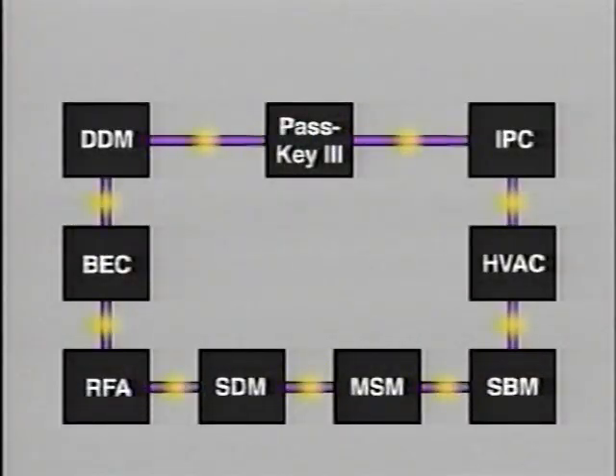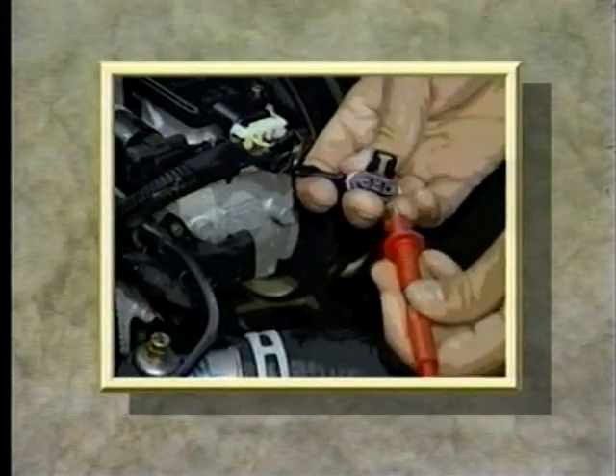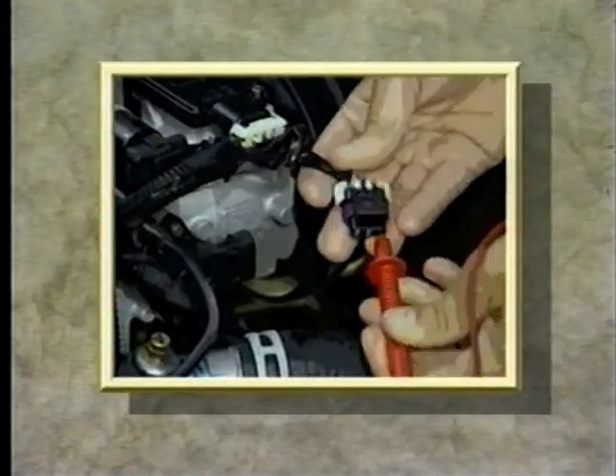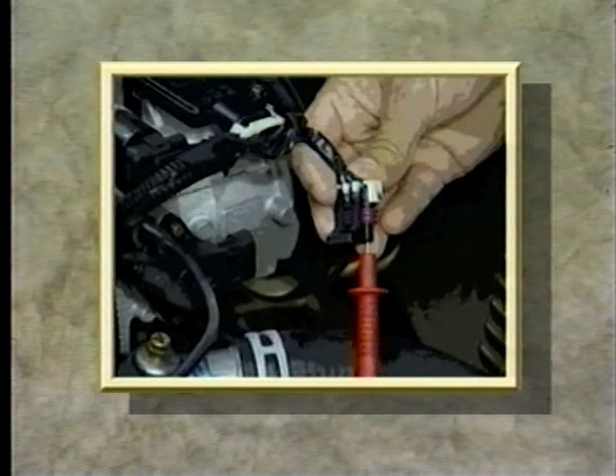In the Park Avenue electrical harness, the purple wire is the data path for the Class 2 system. Unless specifically referred to in the service manual procedures, the purple wire should not be probed or disturbed and should never be used as a source of voltage for any device. The integrity of each connector in this circuit is just as vital as the wire itself to proper operation. Connector terminals can be easily damaged by improper probing, particularly in the bus electrical centers or BECs.